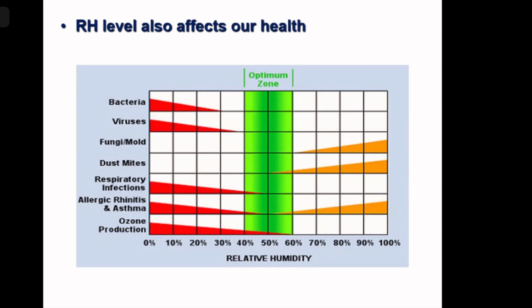There are some infections which increase when you decrease the relative humidity, and there are some infections which increase when you increase the relative humidity. But there is a green corridor, 40 to 60%. For looking at human health, we should keep the relative humidity between 40 to 60%. For the general office areas, general residential purpose areas, we should keep 40 to 60% relative humidity. Next.